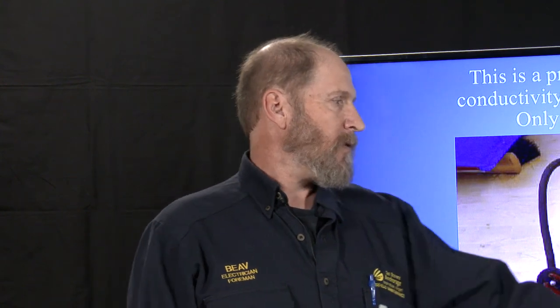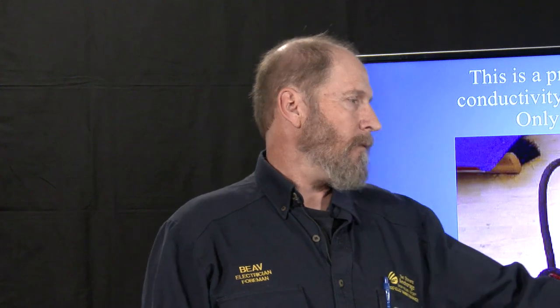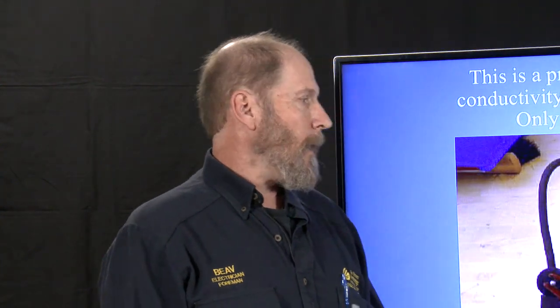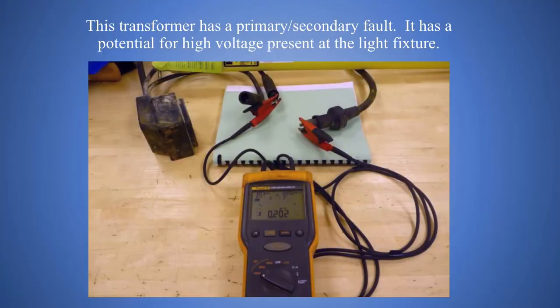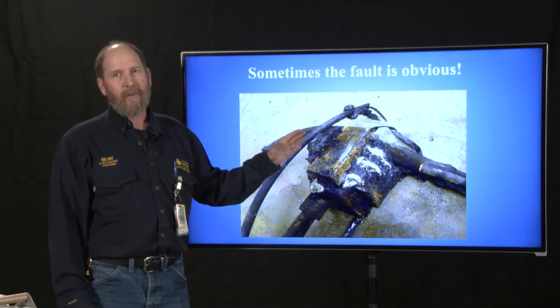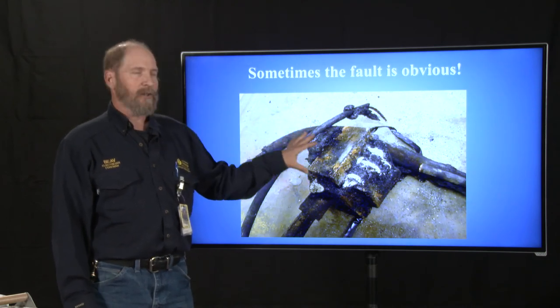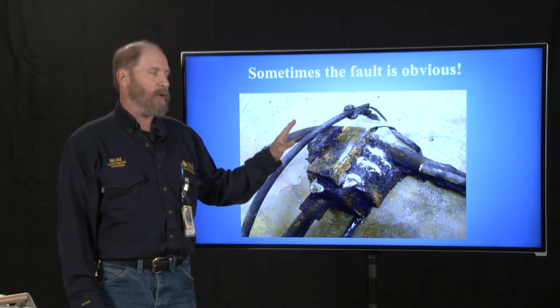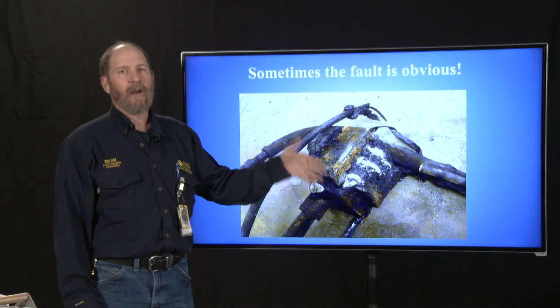So if there was anything wrong with this transformer right here, this megger would give us a lower reading. So we might end up with 200 kilo-ohms, 200,000 ohms, rather than 4,000 million ohms. So it would be lower. Or if there was a dead short in there, we might get even 0 ohms across between the two. But it doesn't take a huge short to allow the high voltage to transfer over to the secondary. Sometimes the shorts or the faults are obvious, and this one obviously has zero ohms between the primary and the secondary. So this one was definitely feeding high voltage up to the fixture.